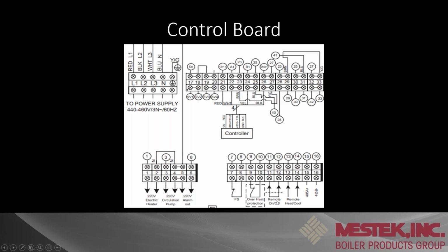So there, you would take a dry contact and you would either close it or open it if you want it on or off. Now, if we're using BMS, you just leave it closed and BMS would control it from there. Now over to 13, 14, that's your remote heat cool. That also, I believe, can stay jumped or we keep it open, but regardless, that's how we put it in heating or cooling.